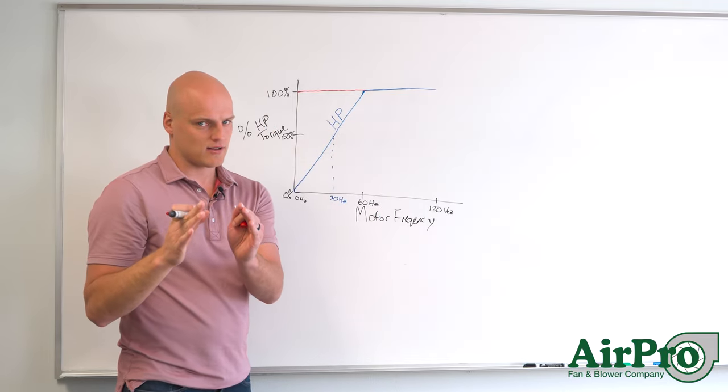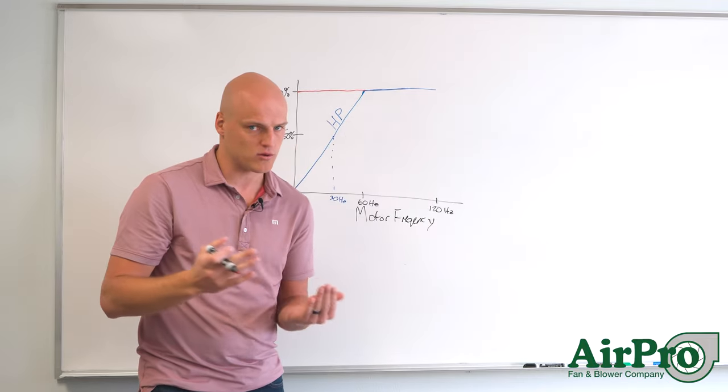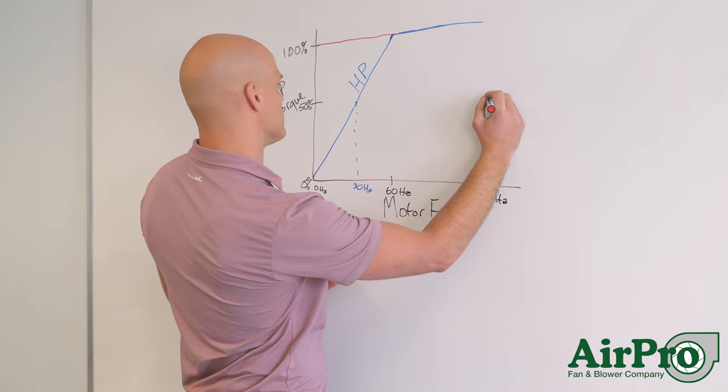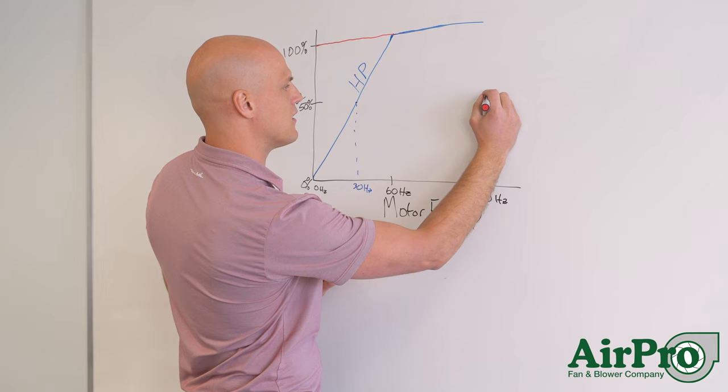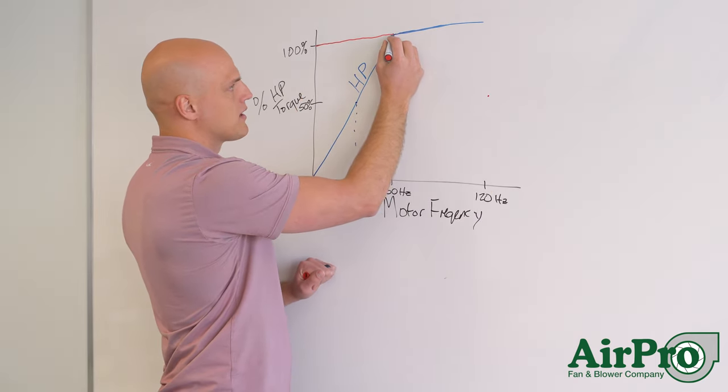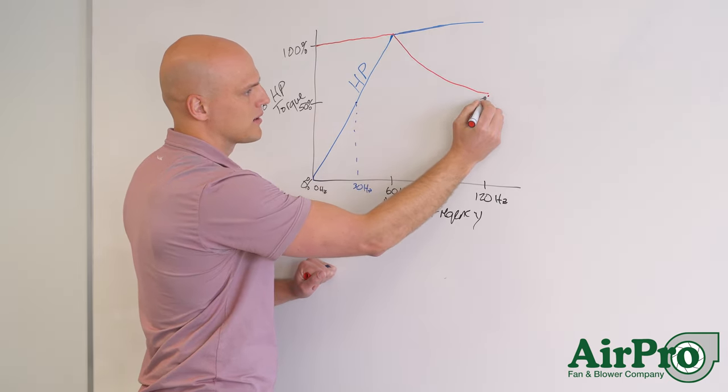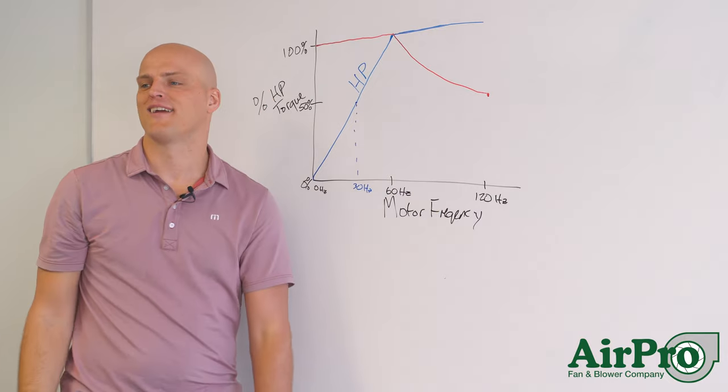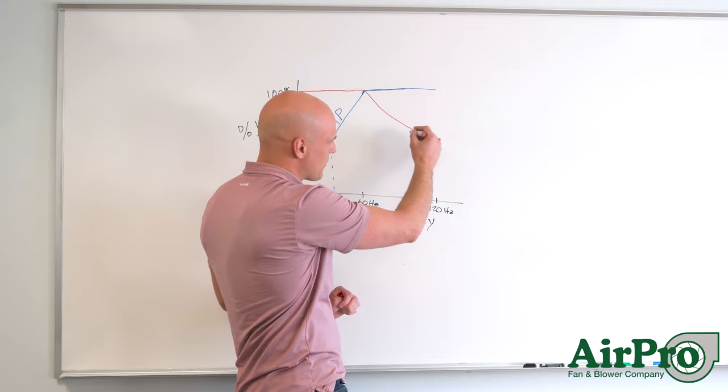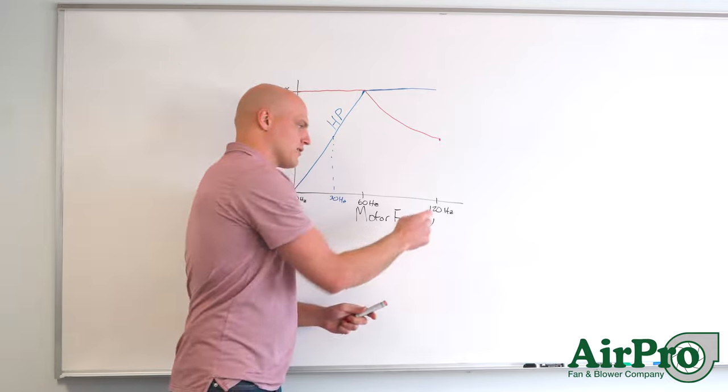That's when torque starts to tail off. So from here out to on a smaller motor that can go up to 120 hertz we're going to come down to 50 percent from this point. And this relationship is a curve that looks like this. So we're coming out and from 60 hertz to 120 hertz we're dipping and we're coming out and we're at 50 percent of the available torque at 120 hertz.